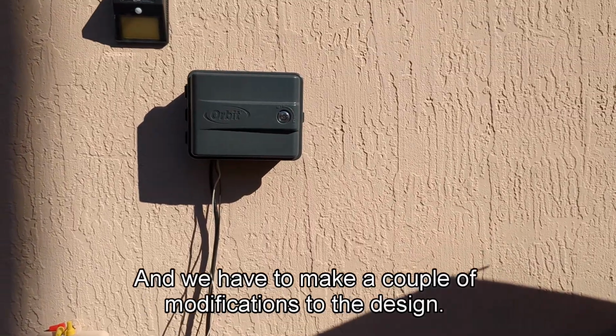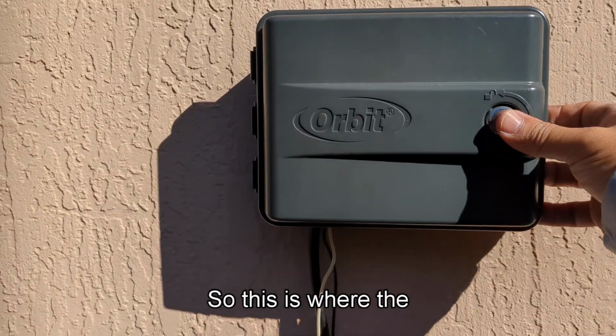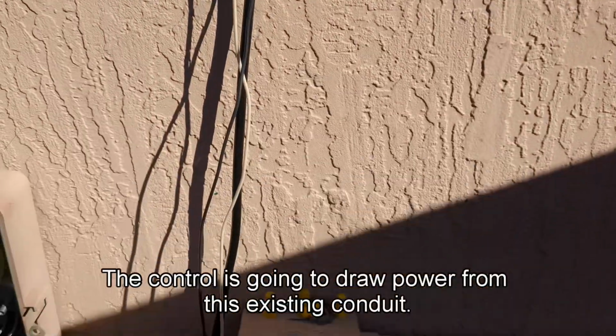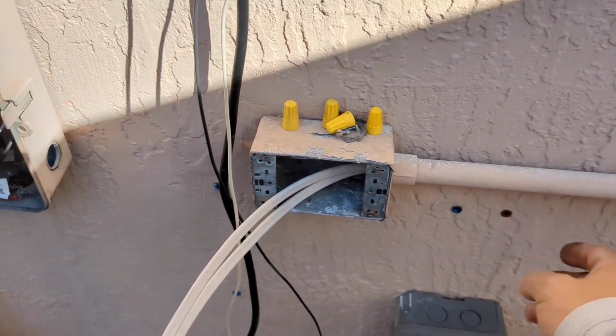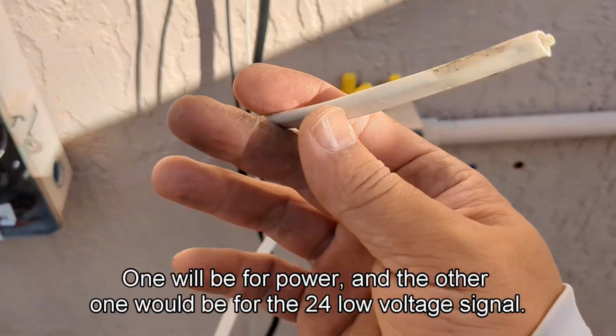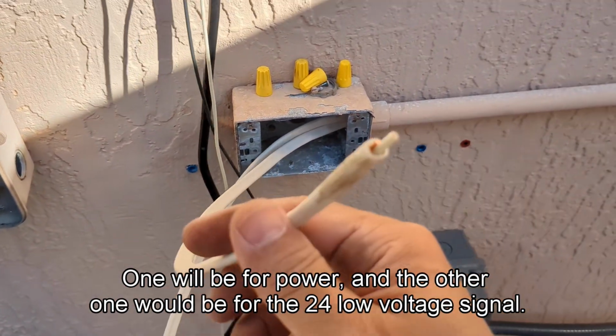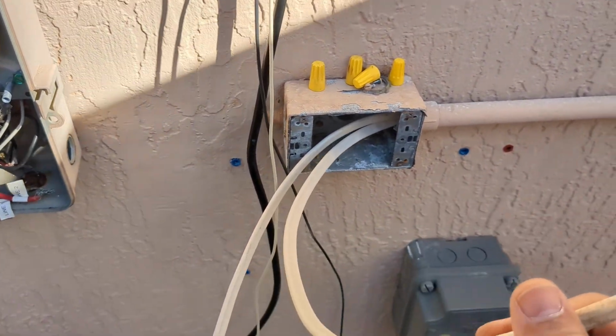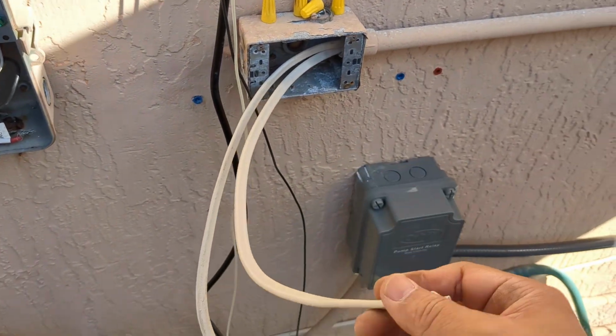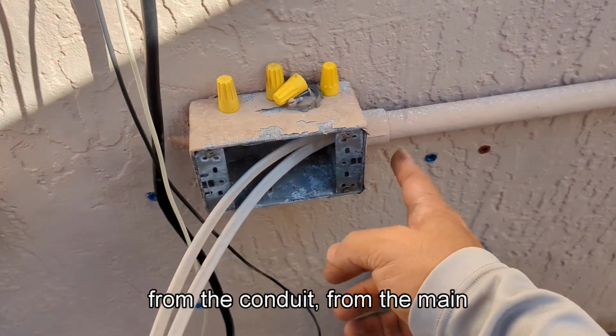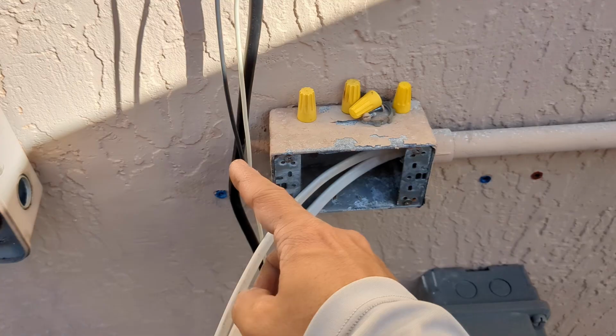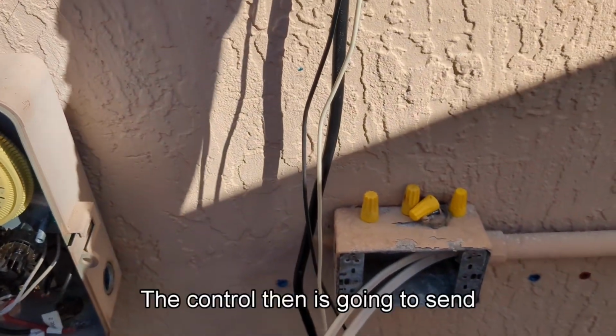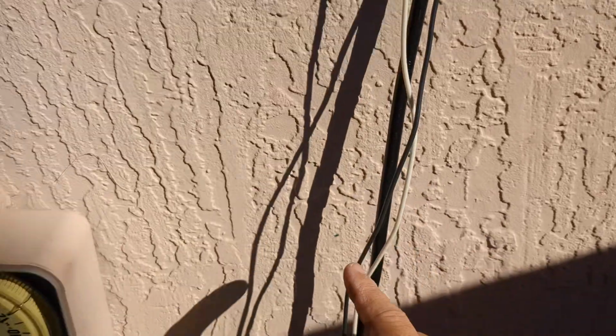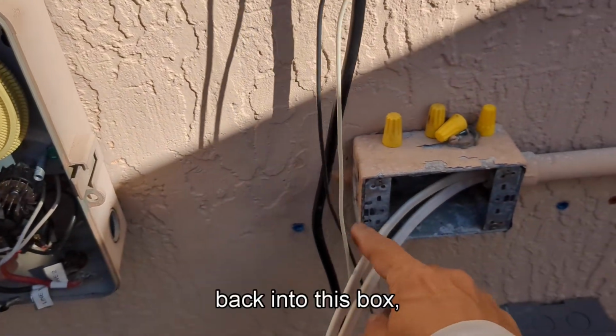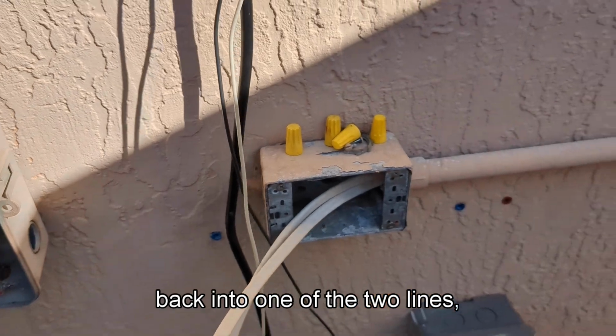All right, we've had to make a couple modifications to the design. So this is where the controller is. The controller is going to draw power from this existing conduit. We pulled two new lines. One will be for power, and the other one would be for the 24 low voltage signal. Now all we have are our number 14 wires, so that's why we're doing this. So power is going to come in from the conduit, from the main box, and it's going to feed the controller.